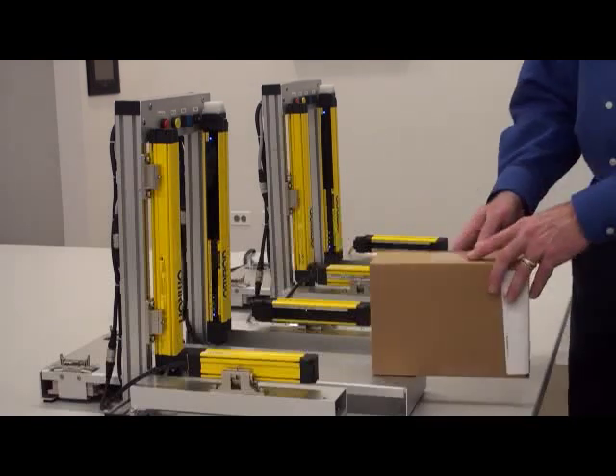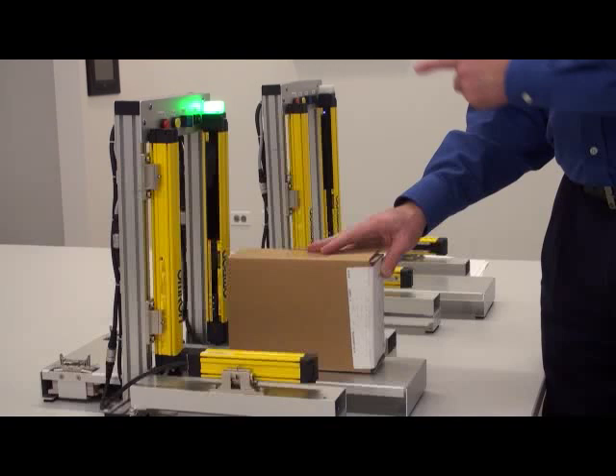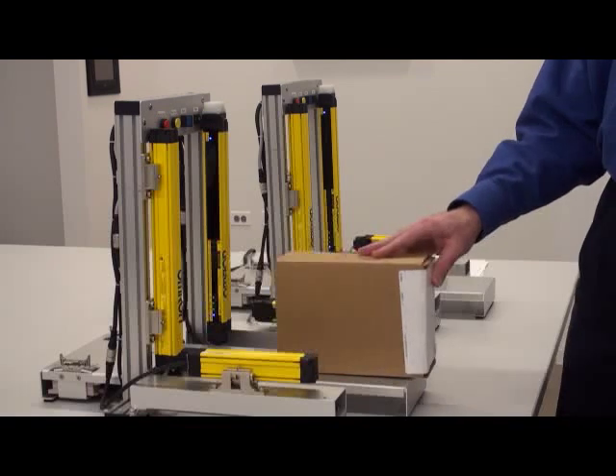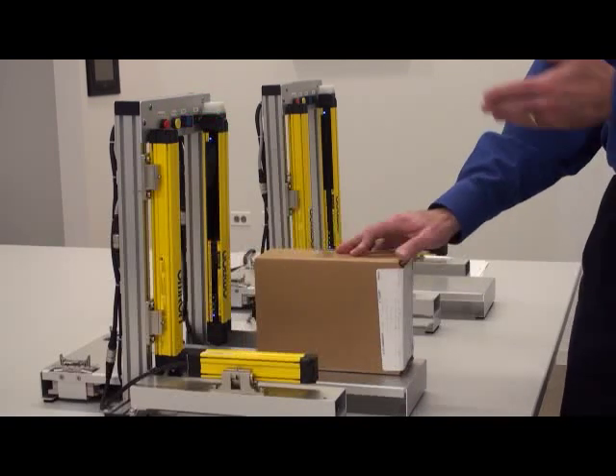If I take a box coming through, it's going to be muted, and as it gets muting, if I pull this back just a little bit, it's going to go off. Here it comes, it starts muting, and then if I come back it shuts off. So the output tripped.